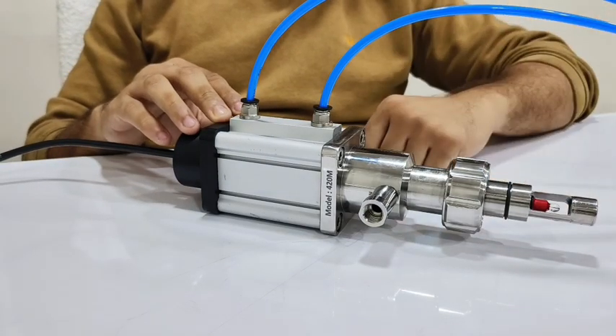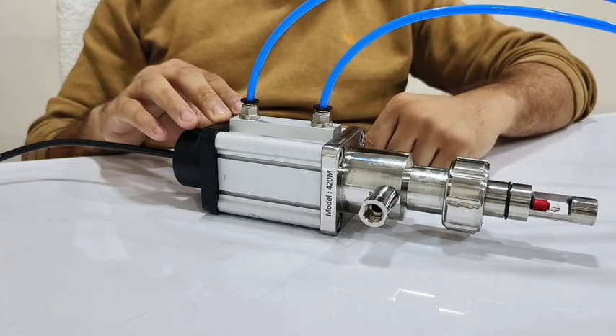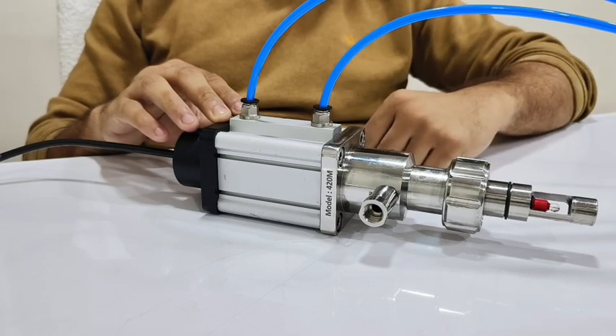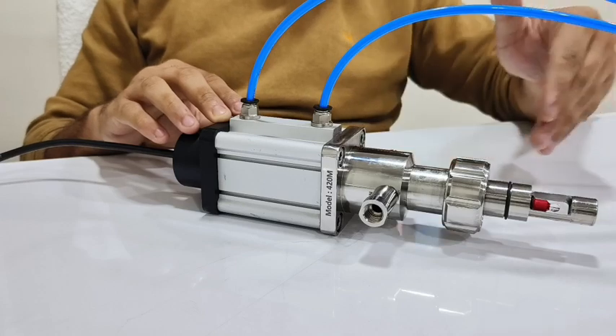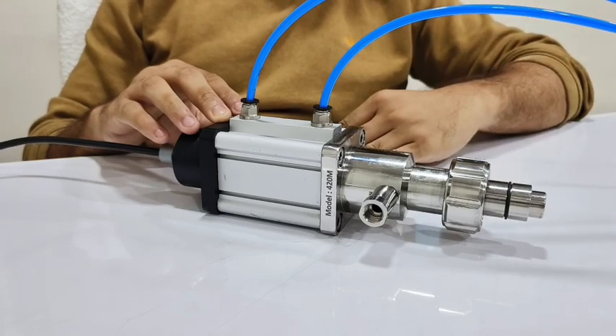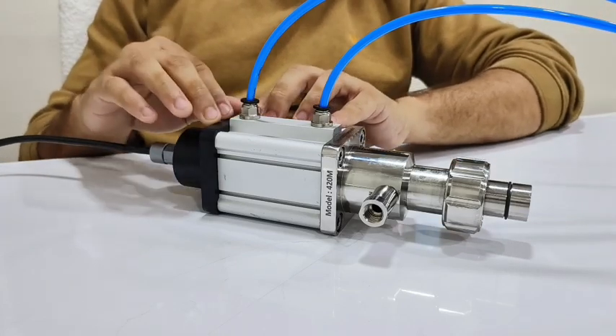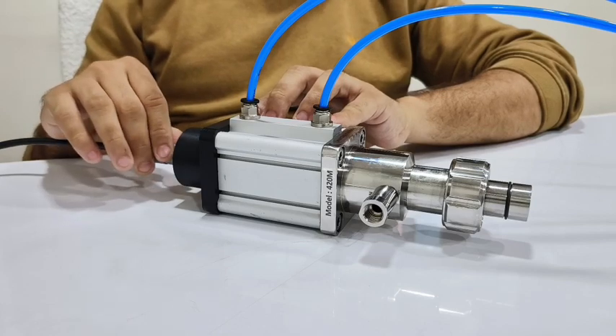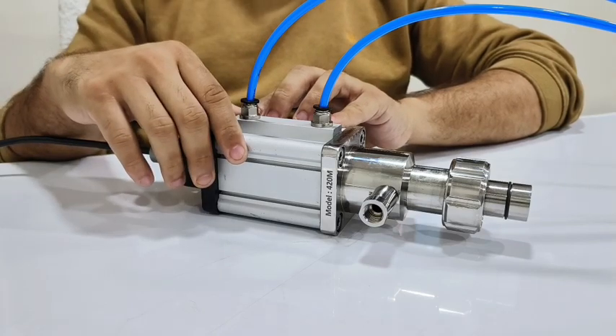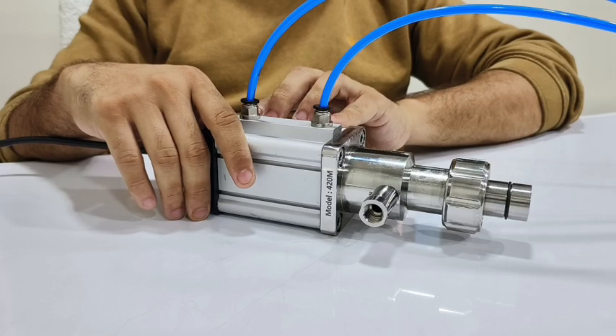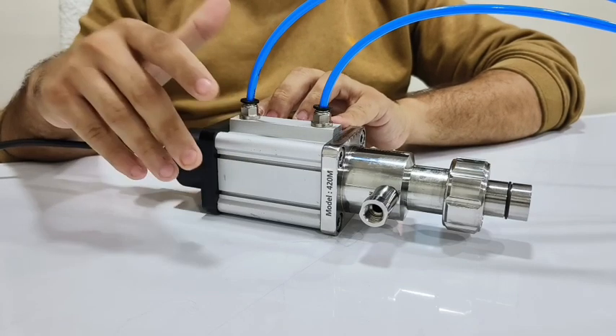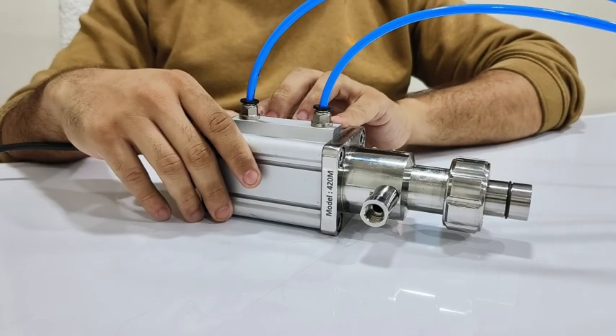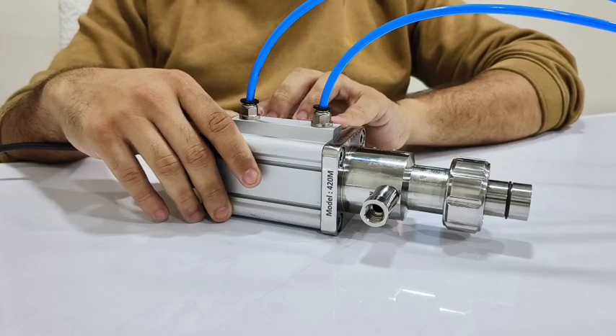be inserted inside of the process. Once you want to perform the calibration or maintenance on your electrode, you can retract it back to the service position and you can perform the calibration. The major benefit our retractable electrode housing provides to the fermenters and bioreactors is the flexibility of sensor maintenance, cleaning, and performing calibration, CIP and SIP cycles without interrupting the process.